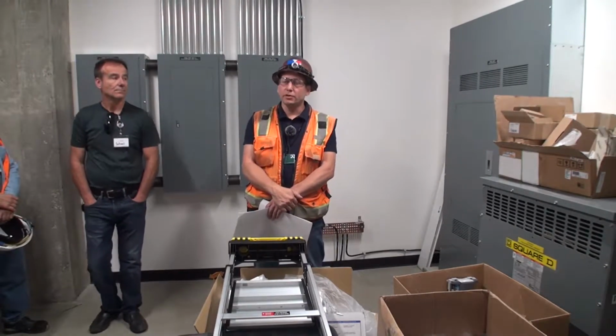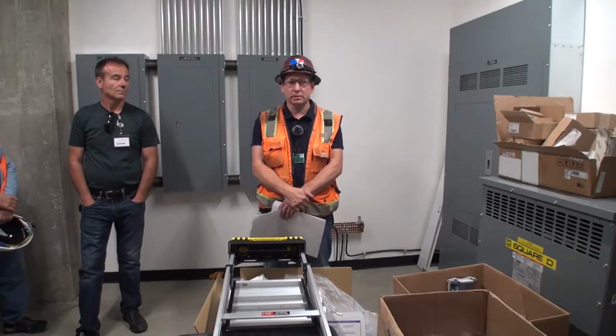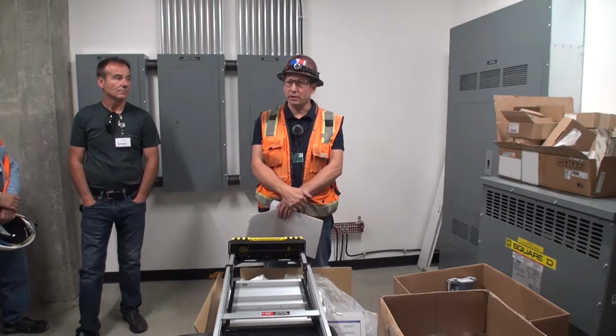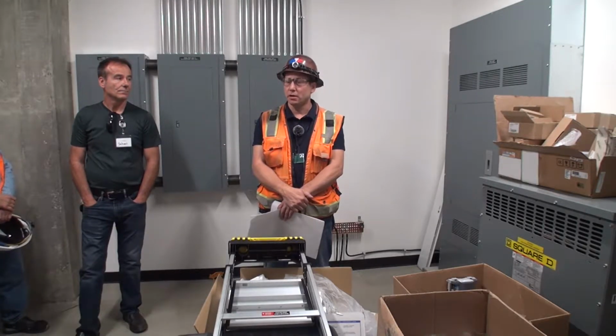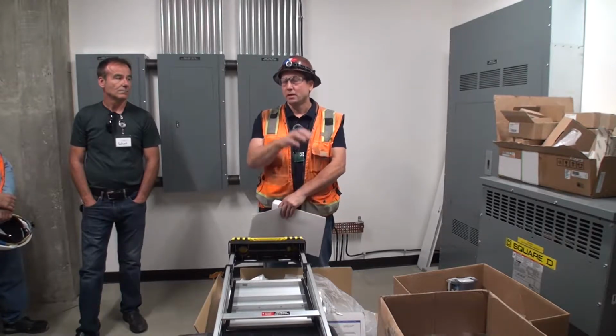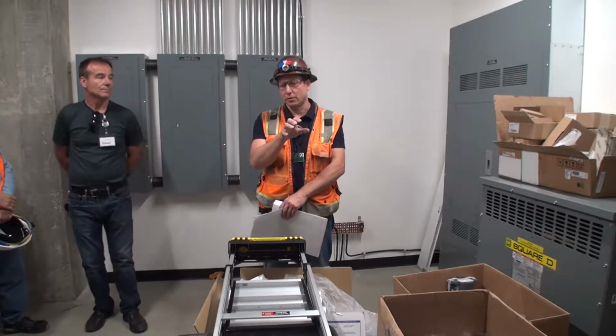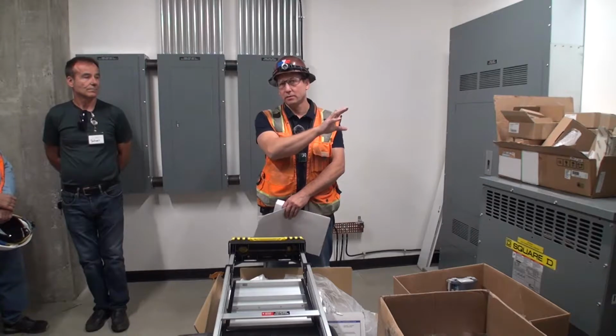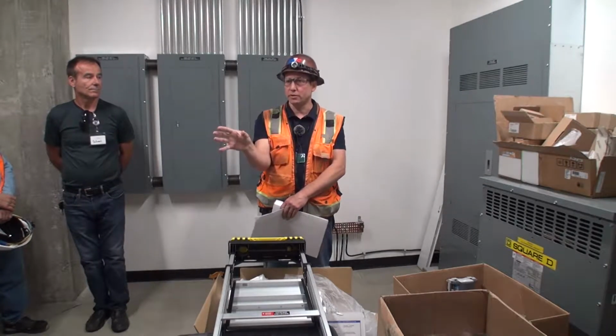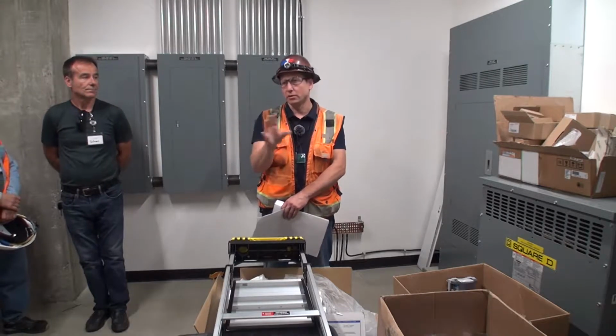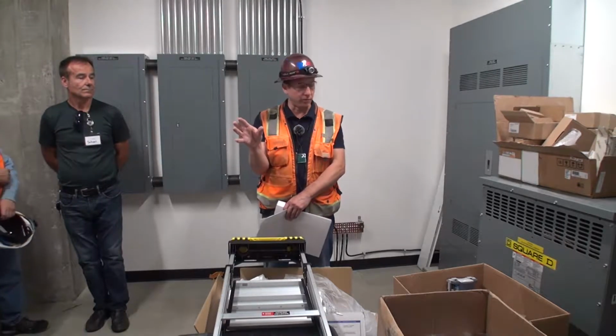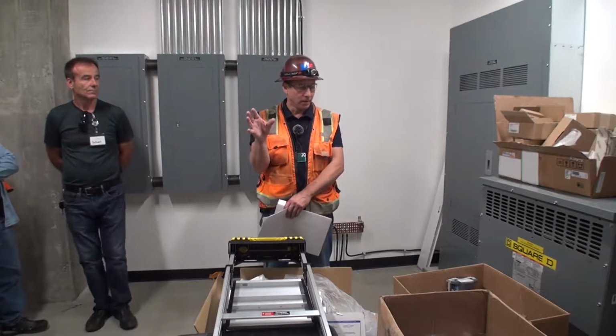Sure, so at the generator there's one 600 amp breaker. It feeds a 600 amp emergency panel. That 600 amp emergency panel then feeds the standby transfer switch, and it also feeds the emergency transfer switch. This is going to be all in the 277, 480 volt range.